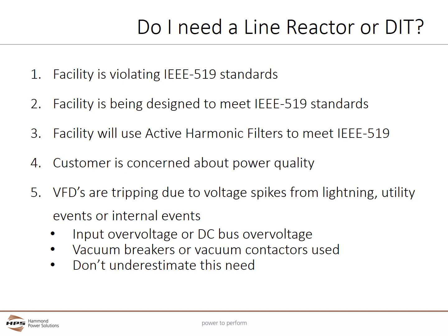Number 2, a facility is being designed to meet IEEE 519 standards. Like number 1, reactors and DITs may be a solution or part of a solution. Number 3, a facility is being designed for meeting IEEE 519 standards and active harmonic filters are being used. Active harmonic filters, like our HPS True Wave, work like noise-canceling headphones. Instead of canceling audio waves with speakers, an active harmonic filter creates harmonics equal to but opposite of those created by the VFDs. Active harmonic filters benefit from each VFD having a line reactor at a minimum. Really, anytime you hear the words IEEE 519, you probably need to consider line reactors or DITs at a minimum.